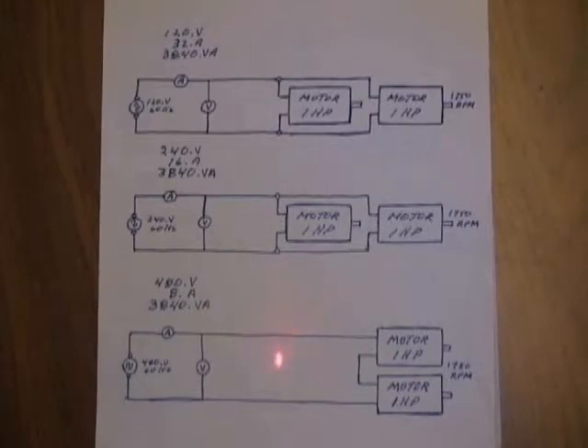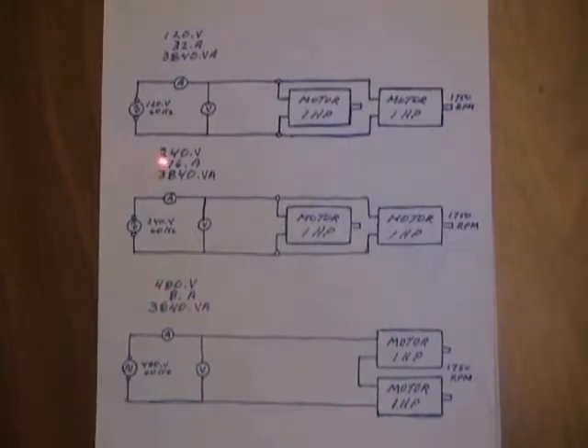Now, in this last part of the drawing, we have the same two motors, but now they are connected in series instead of in parallel as in the above drawings. Here we are going to be supplying them with a source of 480 volts, which gives a requirement of 8 amps instead of 16 amps. Please take into consideration that we are doubling the voltage here, so the current is going to be half of what it was before. But the total of volt amps is always going to be the same. It's going to be 3840.